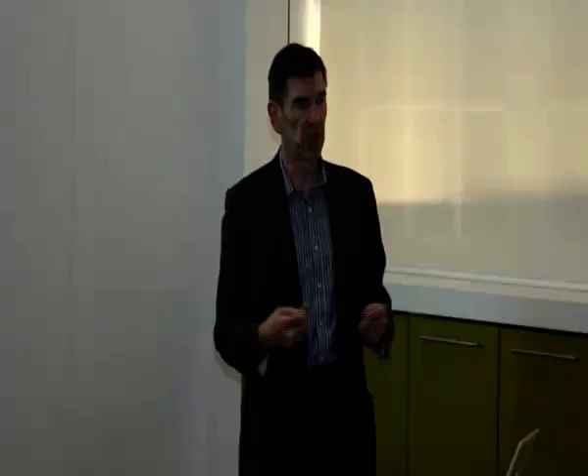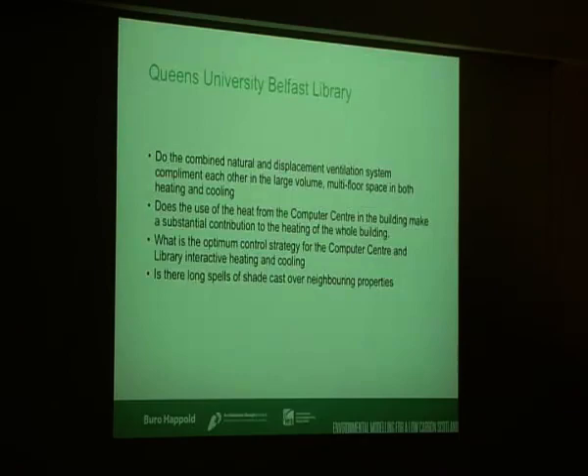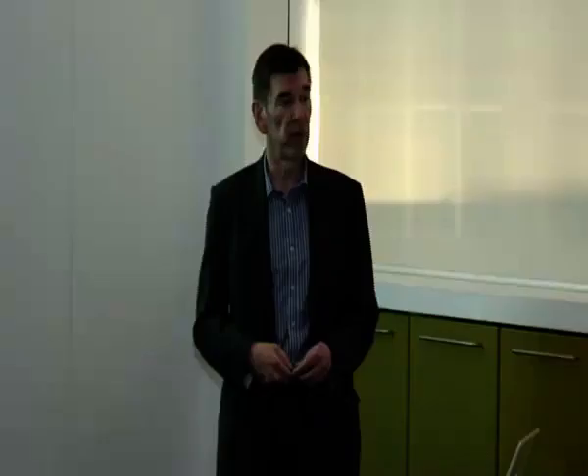Moving out of the range of Scotland now - I've got a couple of projects where we did a lot of good quality computer modelling to prove certain things. This is the Queen's University Library in Belfast. It's a 25,000 square metre library - a low energy design with natural ventilation and displacement in the deep plan areas. But what we had to accommodate was quite a large computer data centre right in the middle of the building. We decided to use the heat from the data centre to heat the library. So there was quite a lot of modelling and simulation to prove that could work. The questions for us were: how effective would the natural ventilation be in cooling the space in these large volumes, and how would the interaction of heat from the computer centre work across the building?